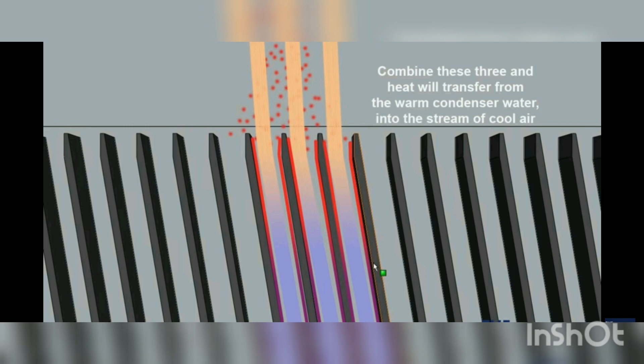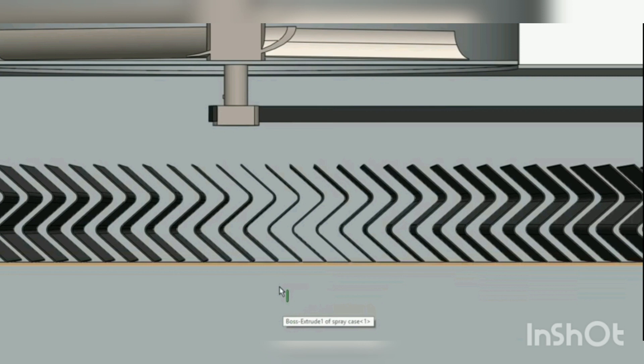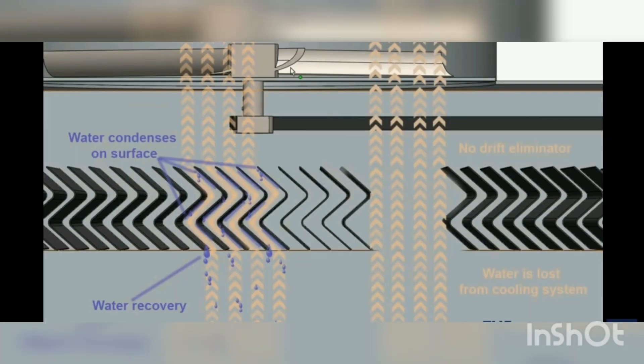Here is the drift eliminator discussed earlier. Due to its shape, as air containing water droplets strikes it, the moisture loses energy and condenses out. You can see small blue droplets representing the condensing water. On the right-hand side, you can see that without a drift eliminator there would be no recovery of that water. So the basic purpose of the drift eliminator is to recover water that would otherwise be lost.